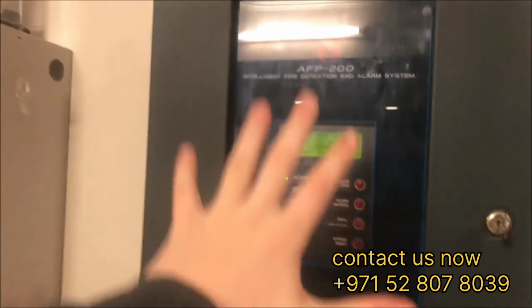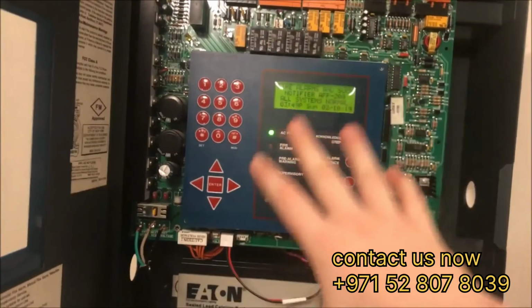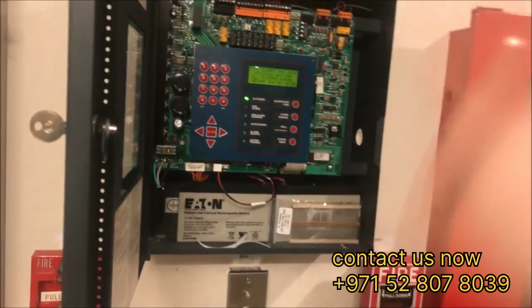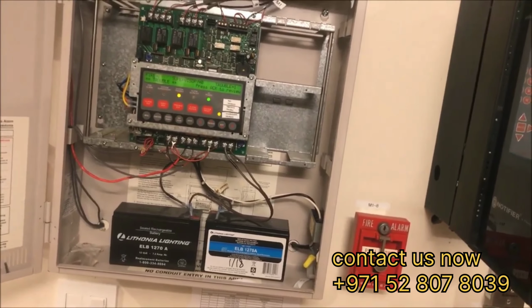Now the downside to these is the cost, complexity, and that these will only work with their own devices. A conventional panel will work with any conventional device. But an addressable panel will only work with modules that are from this manufacturer. So like I have 2 addressable panels. A Simplex module is not going to talk to a Notifier panel. A Notifier module is not going to talk to a Simplex panel. You need different devices that speak their own language. Each one speaks a different language, or protocols it's called.